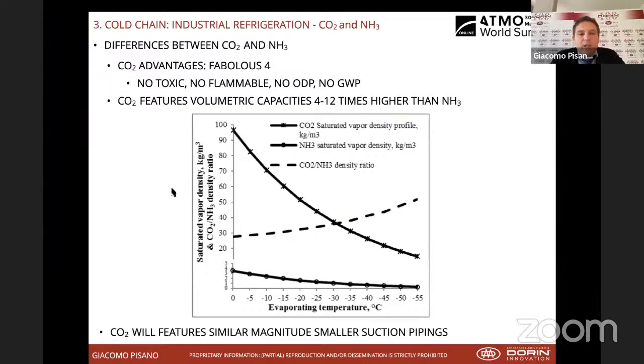Another big difference between CO2 and ammonia is a very high volumetric capacity, very high specific refrigeration capacity, which is from 4 to 12 times higher than ammonia, depending on the operating conditions. And this brings a big advantage for contractors and end users, because you will have much smaller piping. Smaller piping clearly means less cost, but also very easy construction work, very easy maintenance. The diameters of the pipes are much smaller, so they cost less, but they are also much easier to install.